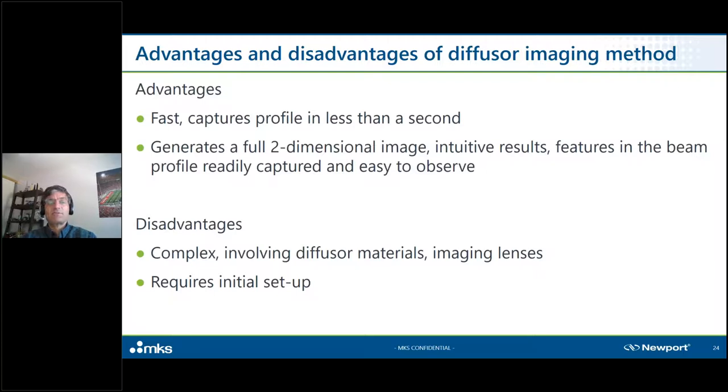You're basically taking a snapshot of the beam, so if you're looking for shape or mode structure or some sort of variations in the profile, it's very easy to capture and observe them. And in addition, you can analyze the images captured by this technique to get measurements like beam size and divergence.